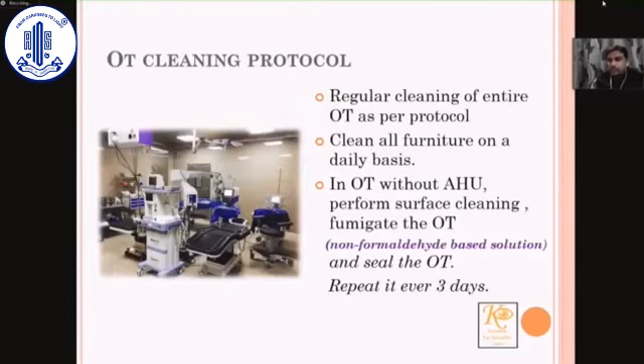There isn't any change to the cleaning protocol of your operation theater and the furniture, even during periods of shutdown. They have to be cleaned on a daily basis. However, during the shutdown, you can probably clean it once in 3 days. Suppose in OTs where they don't have an AHU, then the OT has to be cleaned as per protocol. Then they have to be fumigated with a non-formaldehyde-based solution, and it has to be sealed. This process has to be repeated once in 3 days during your periods of shutdown.